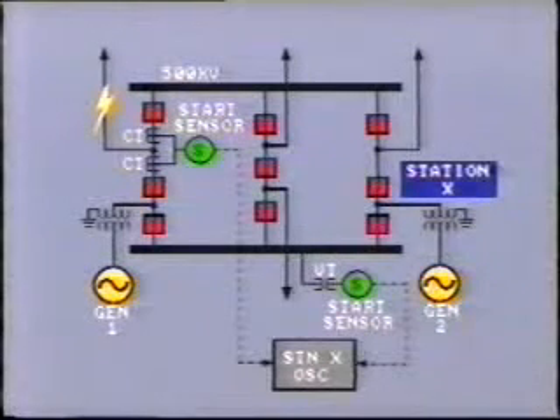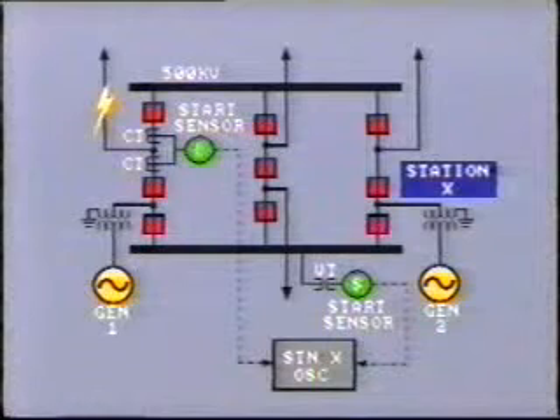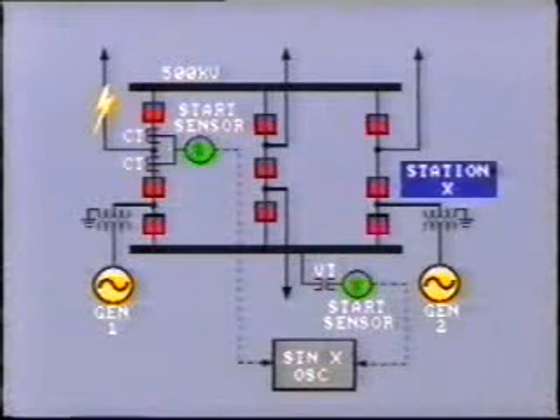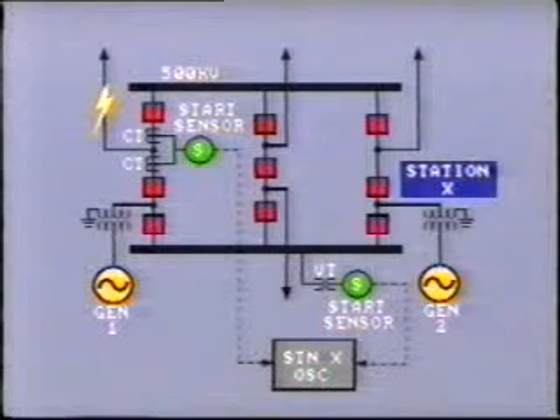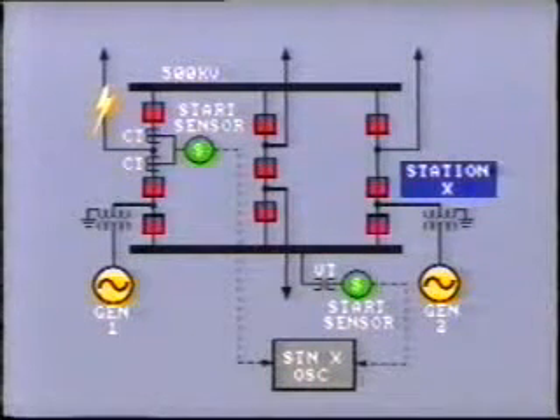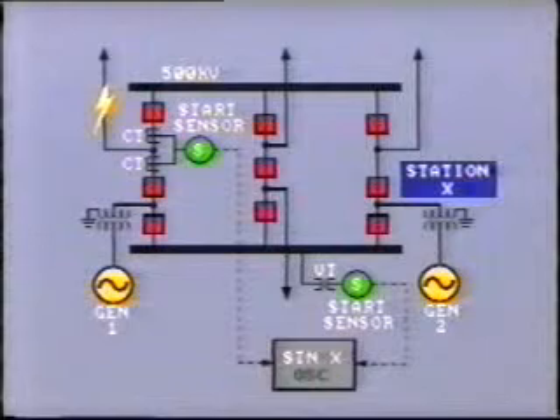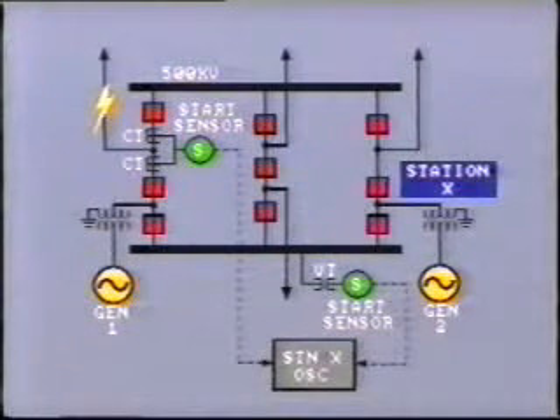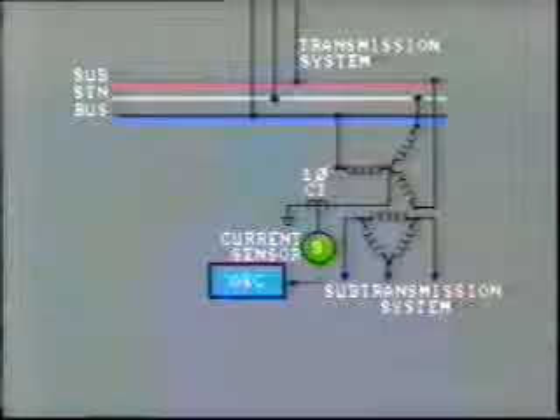The most important accessory is the starting sensor. The sensor is basically a relay which continuously monitors the power system and detects disturbances such as faults and power swings. The sensor signals an oscillograph machine to start recording. Fault sensors are the most common type. Now, they typically respond to overcurrent or undervoltage.